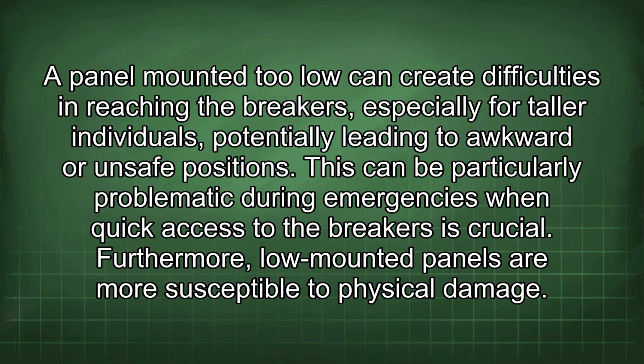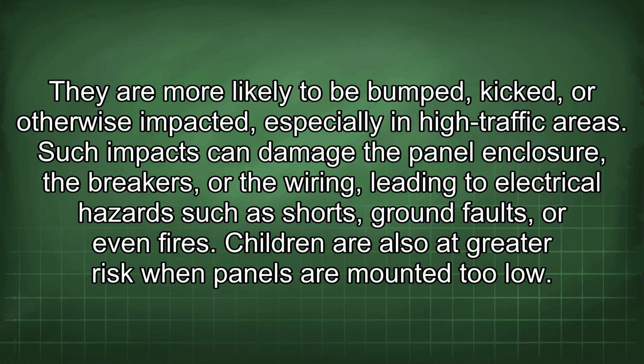A panel mounted too low can create difficulties in reaching the breakers, especially for taller individuals, potentially leading to awkward or unsafe positions. This can be particularly problematic during emergencies when quick access to the breakers is crucial. Furthermore, low-mounted panels are more susceptible to physical damage. They are more likely to be bumped, kicked, or otherwise impacted, especially in high-traffic areas.